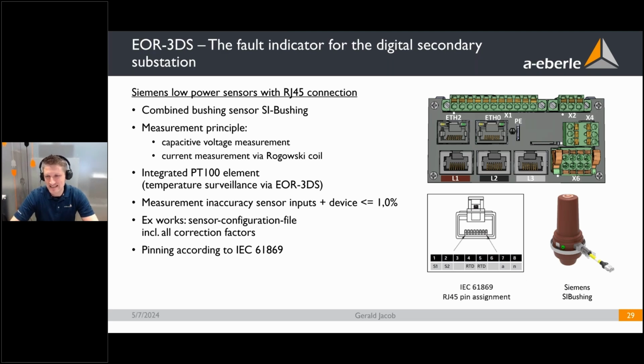Here in comparison, the Siemens SI bushing is relatively new, so it is directly according to the IEC standard 61869. As you can see here, the current is on pins 1 and 2, and there are additional pins used, 4 and 5. And what are they used for? They are used for an internal PT100, so a temperature sensor that is read out from the EOR-3DS. So the EOR-3DS can measure not only the voltage and the current per phase, but also the temperature of each bushing. So this is a quite nice feature.